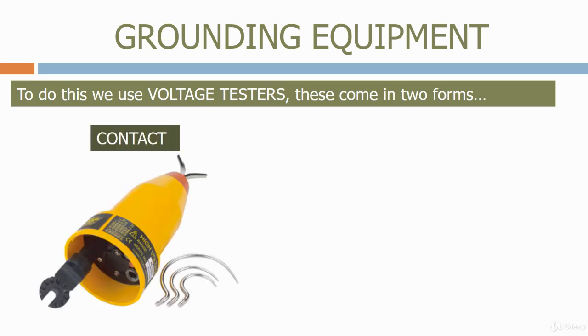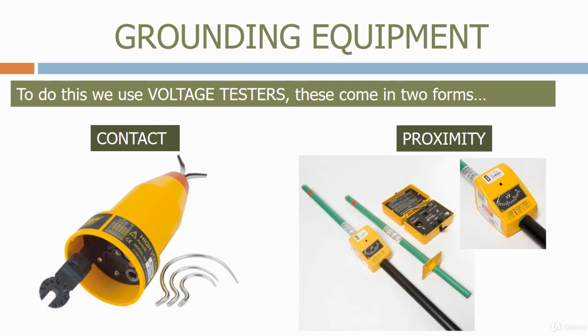We have voltage testers that make a direct contact with a circuit that needs to be grounded. These tend to be used on distribution circuits up to 36 kV. Above this voltage level, it becomes too dangerous to make a direct connection to the circuit. At these higher voltage levels, we use voltage detectors that detect a voltage by being in proximity to the line that we intend to ground. Both of these types of detectors produce an audible alarm if voltage is present on the line being grounded.